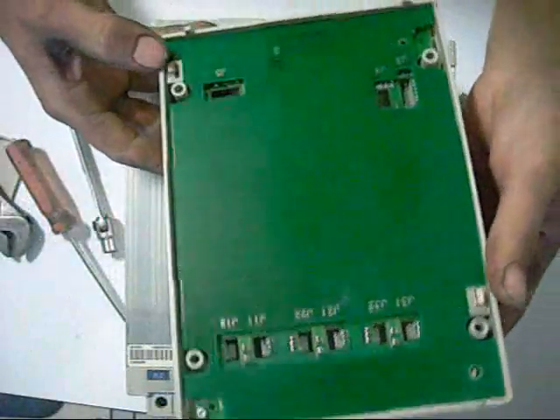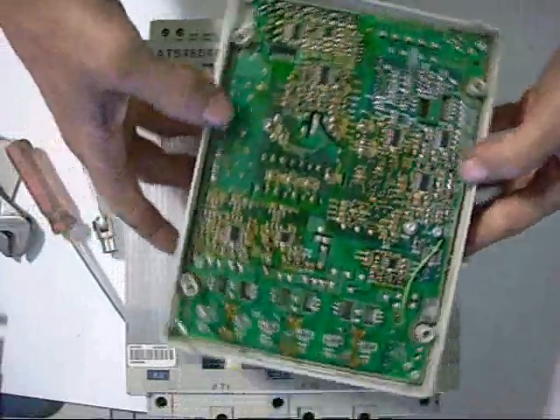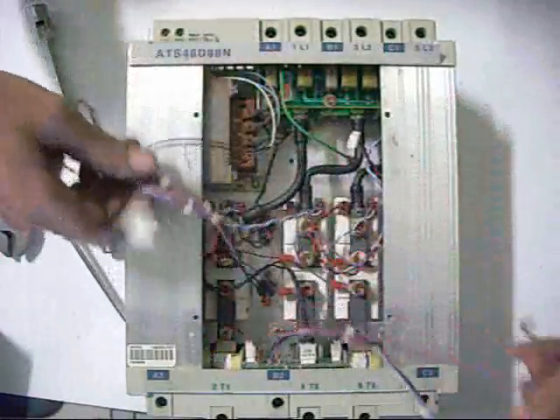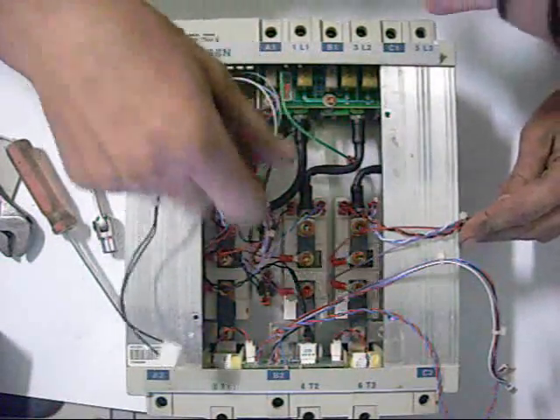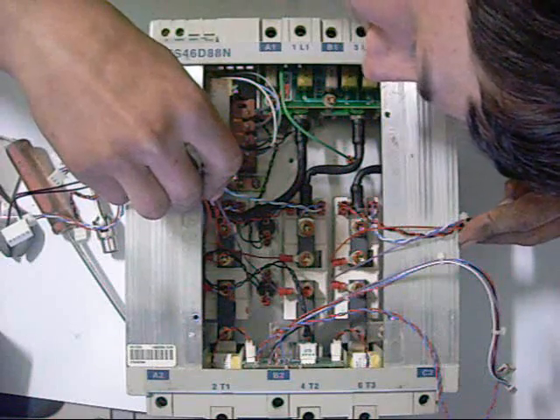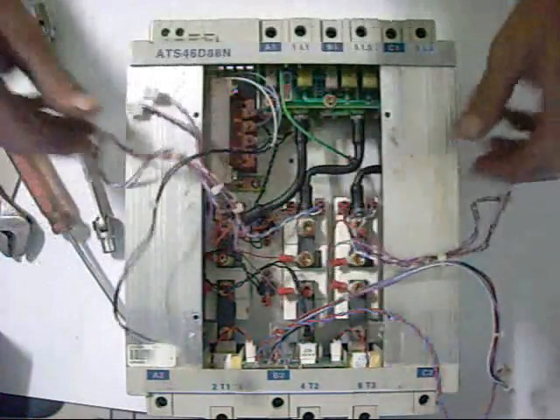Here's the control box — what a surface mount componentry. There are the bricks, made by Semikron, Semi-Pak 2, SKKT 1G2-14E — that's what they are. There's been a lot of moisture getting in there too, there's corrosion on it. There are current transformers in there, and a power supply transformer for the control. There's not a lot in there.